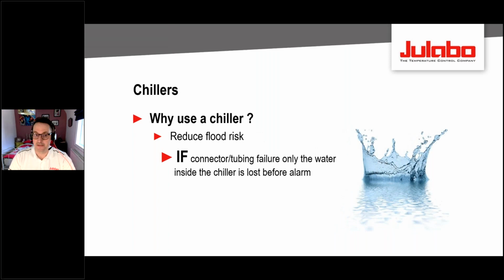And finally, reducing flood risks. We've had stories from labs where hosing has come off a condenser or tap, and that tap has run over the weekend or overnight, flooding labs and causing significant damage. With a chiller, hosing can still come off, but a chiller only holds 3 or 4 litres of water, so the potential damage is significantly less than a tap running all weekend.